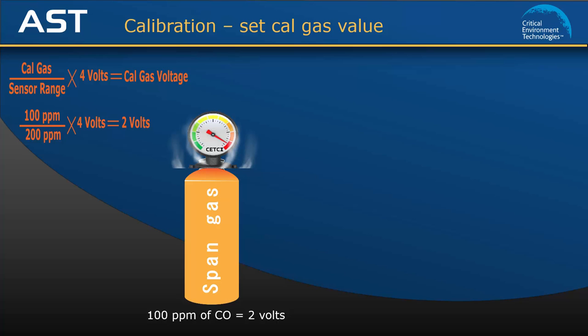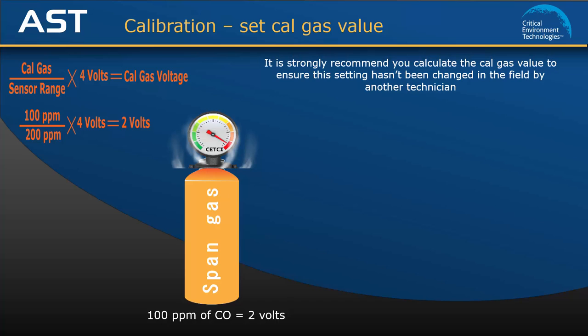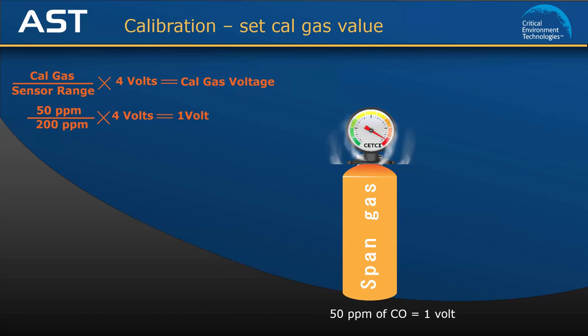Although the factory default is set to 2 volts and corresponds to 100 ppm of calgas concentration, we strongly recommend that you calculate the calgas value to ensure this setting hasn't been changed in the field by another technician using a different calgas concentration. For example, in a situation where you might have a different calgas concentration in your toolkit, you will need to use the formula to calculate the correct voltage so the unit knows what reference to use. If you are using a 50 ppm concentration, you will calculate that the calgas value should be set to 1 volt.